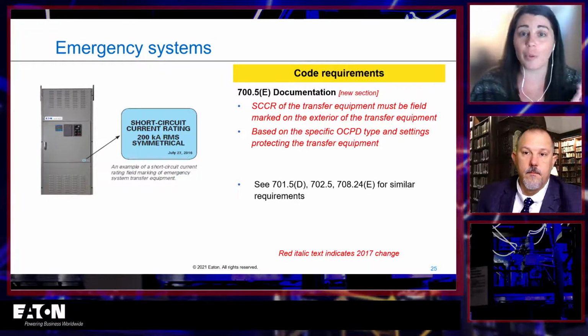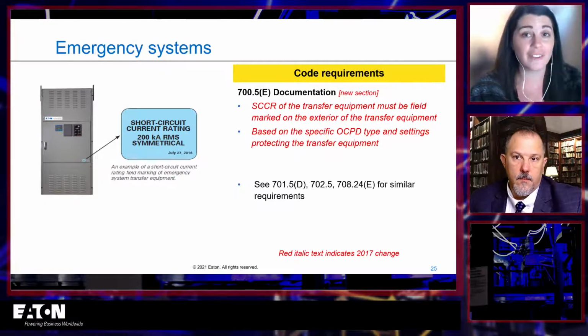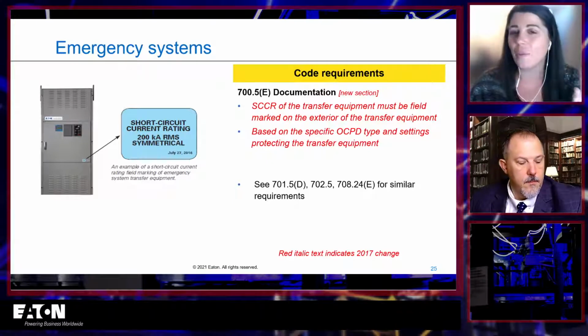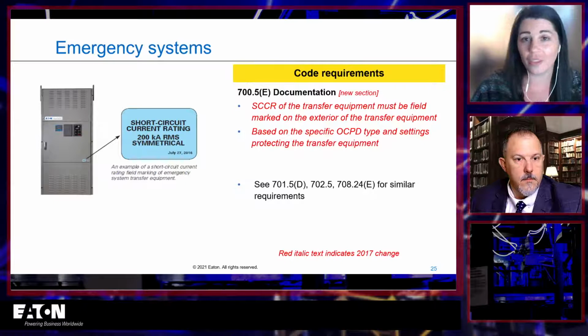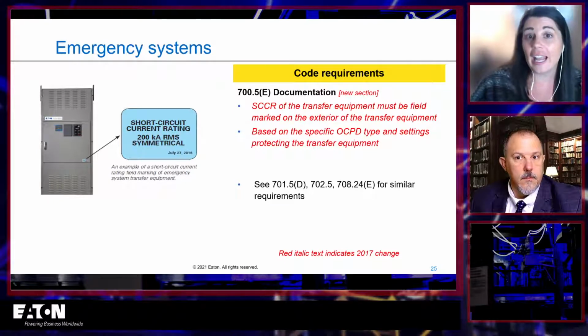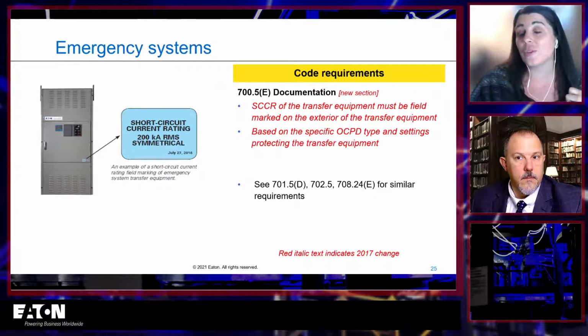But this is actually an example where the SCCR is field marked. And you might say, wait, that doesn't make any sense, right? Doesn't the manufacturer tell me what the short circuit current rating of this is? And the answer is yes, they do. And this is how they do it.